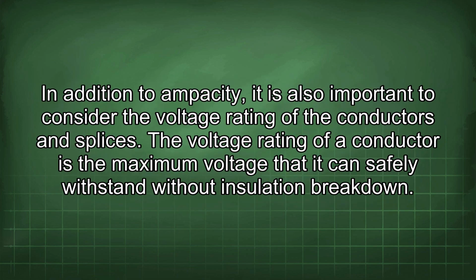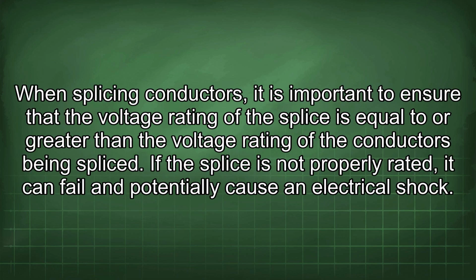In addition to ampacity, it is also important to consider the voltage rating of the conductors and splices. The voltage rating of a conductor is the maximum voltage that it can safely withstand without insulation breakdown. When splicing conductors, it is important to ensure that the voltage rating of the splice is equal to or greater than the voltage rating of the conductors being spliced. If the splice is not properly rated, it can fail and potentially cause an electrical shock.